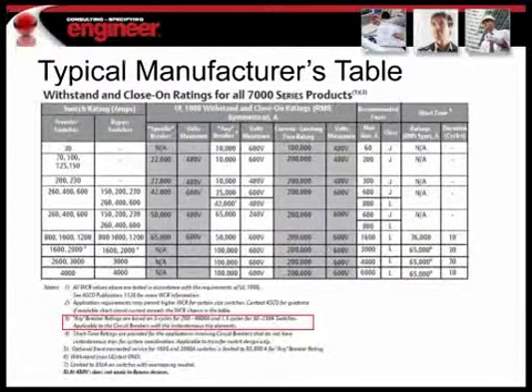And for switches greater than 60 amps and larger, the UL 1008 test involves testing the withstand rating at 3 cycles. Another important point to note is that some of the withstand ratings published by transfer switch manufacturers are not in fact withstand ratings as defined by UL 1008. So you need to be aware that some of the published information is only for withstand ratings and not withstand and close-on ratings. You just have to be sensitive to the information that's published in these tables.